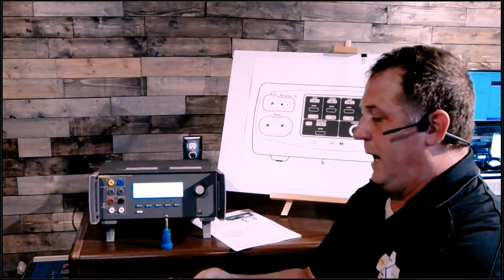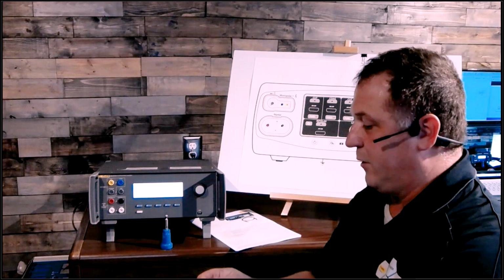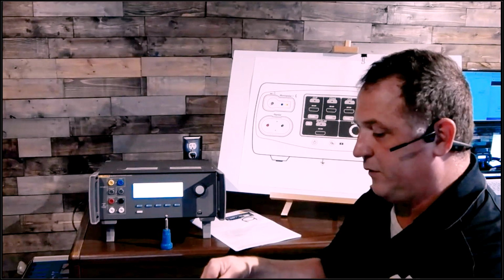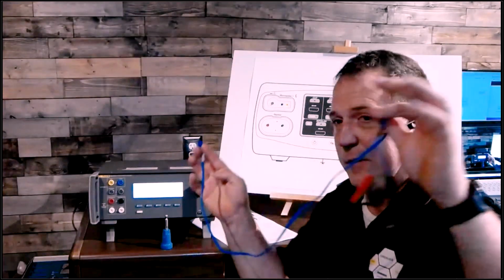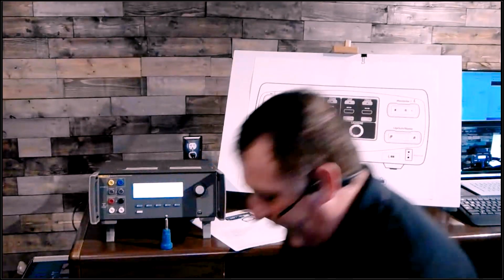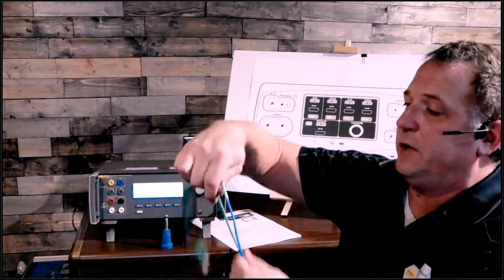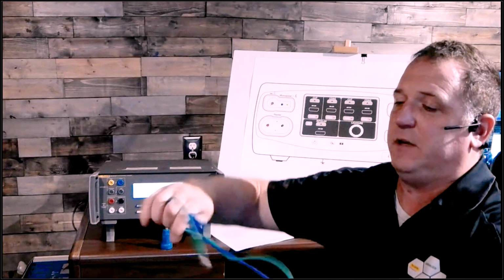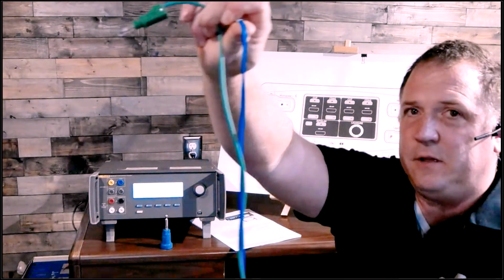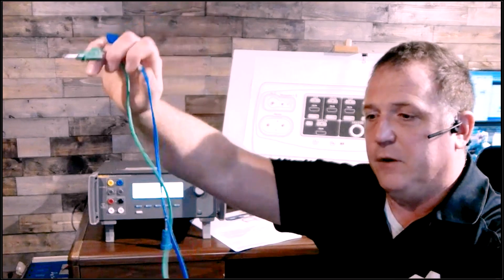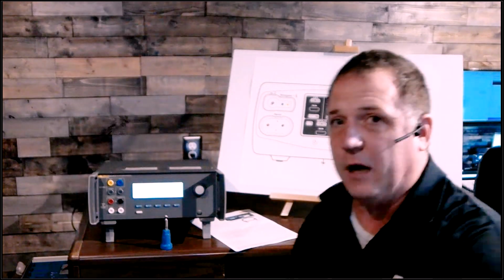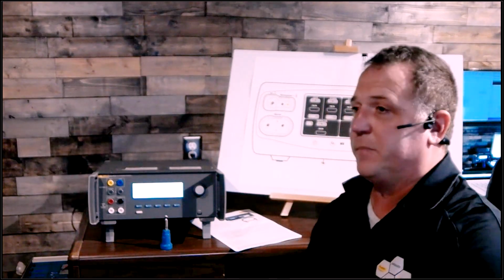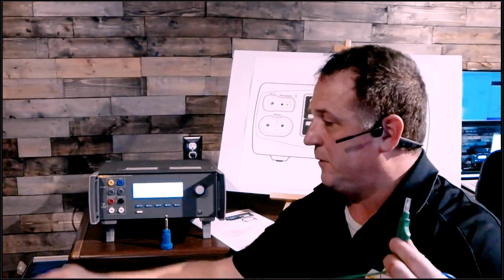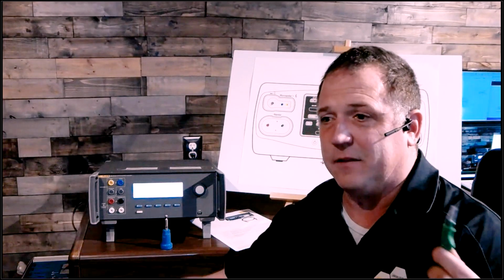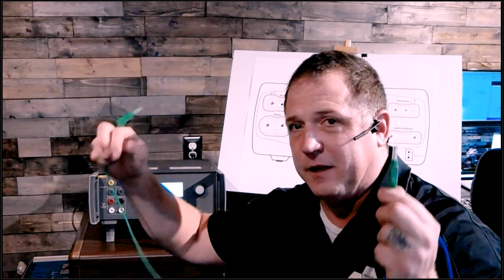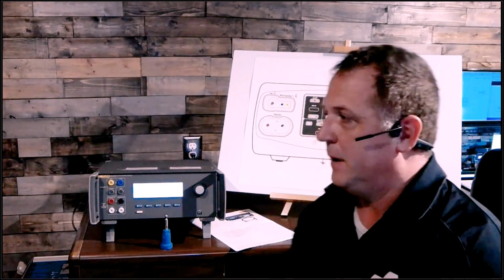Now, in high frequency — and everybody who has an RF generator, radio frequency generator, knows — you have to be very mindful of your cables, because as you cross or intertwine them, remember these high frequencies will transmit from one to the other and can throw off your readings. So you want to make sure your cables are not crossed at all, if possible. The next thing, we talked about this earlier: we don't want to add any length, because we just turn it into a larger antenna and transmit more energy.